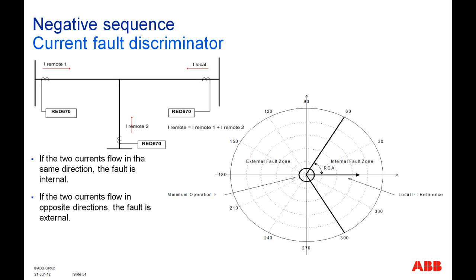So if the fault is inside the protection zone, then these two, or three in case of three terminal lines, all these phasors will be in line together in the same direction, and the relative angle between the local current and the remote current will be equal to 0 or a little bit more than that. So these phasors will be falling in this region, and that is the internal fault zone. And if the fault is outside the protection zone, then the phasors will be falling in this region of the fault discriminator, and the fault will be declared as outside the protection zone.